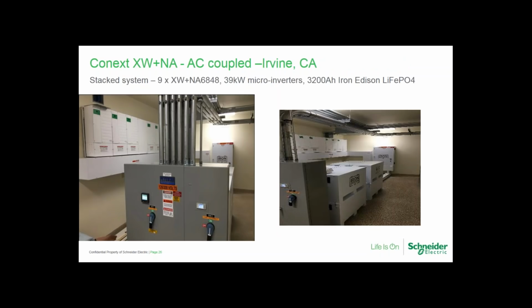Here we can see an XW MultiCluster that is located in Irvine, California, incorporates 9 XW plus 6848 configured for 120/208 three-phase. We have 3,200 amp hours of lithium iron phosphate capacity provided by Iron Edison. And of course, you'll see the AC combiner there at the forefront. So this provides a point of interconnection and bus bars for the XW system, which is bidirectional in function.